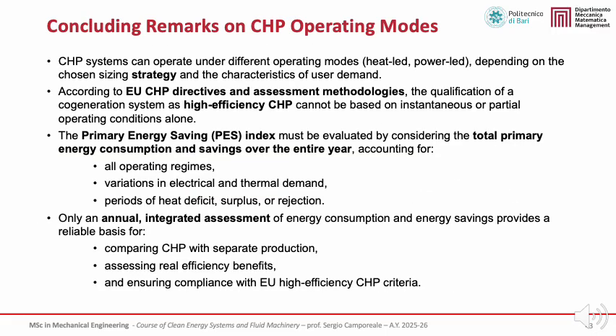To conclude, it is important to emphasize that CHP systems can operate under different operating modes, such as heat-led or power-led operation, depending on the chosen sizing strategy and on the characteristics of the user demand. According to European CHP directives and the associated assessment methodologies, the qualification of a cogeneration system as high-efficiency CHP cannot be based on instantaneous or partial operating conditions alone. Instead, the Primary Energy Saving Index, or PES, must be evaluated by considering the total primary energy consumption and savings over the entire year.